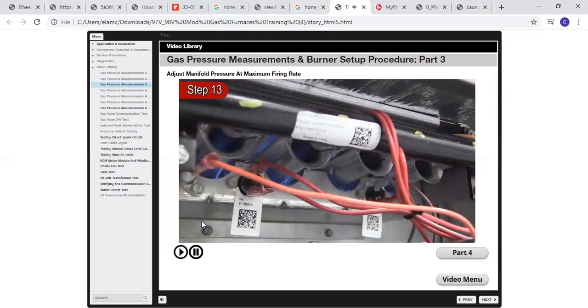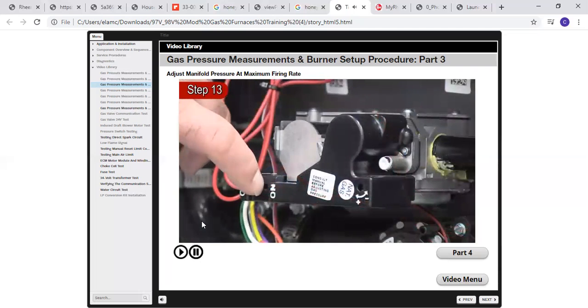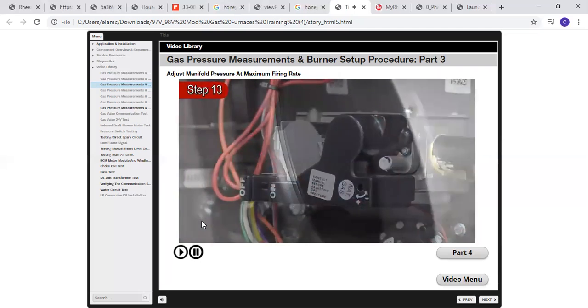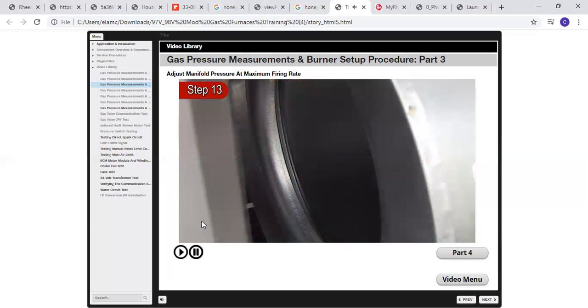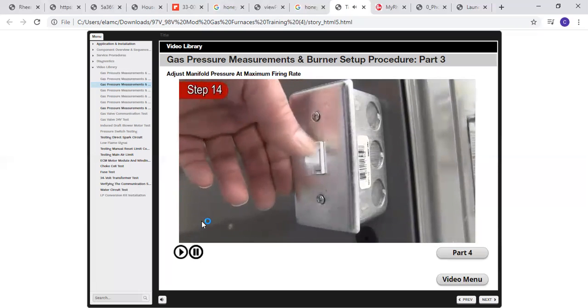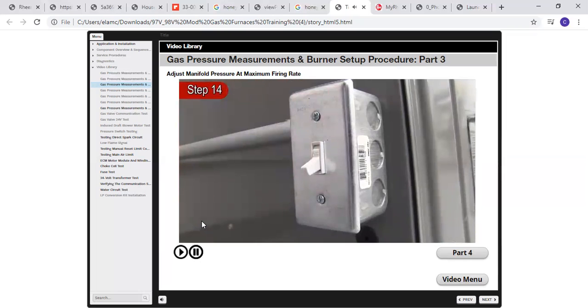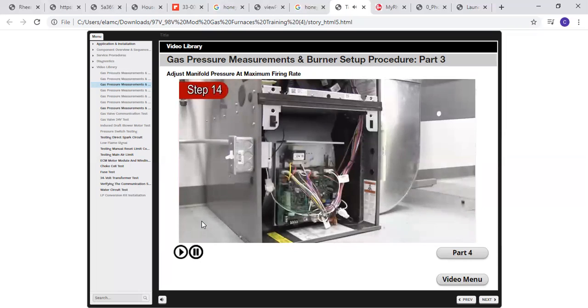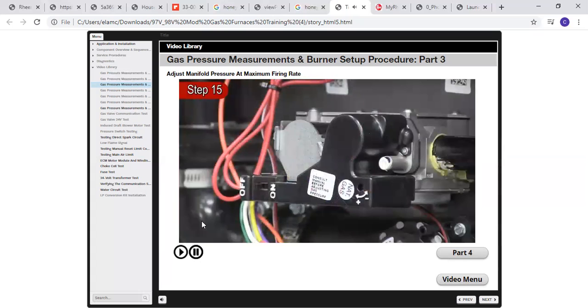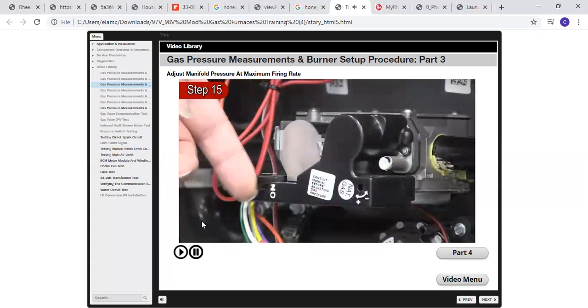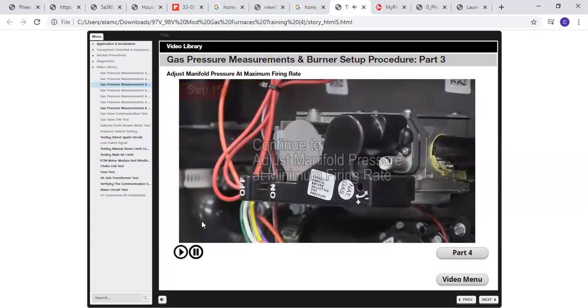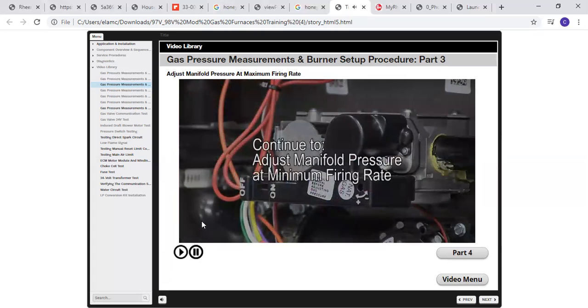Step 13. Once high fire manifold pressure has been adjusted, slide the gas valve on-off switch to the off position. Allow the indoor blower to complete its off delay. Step 14. Disconnect electrical power to the furnace. Remove the blower door. Step 15. Slide the gas valve on-off switch to the on position. That's the setup for the maximum fire rate setting.